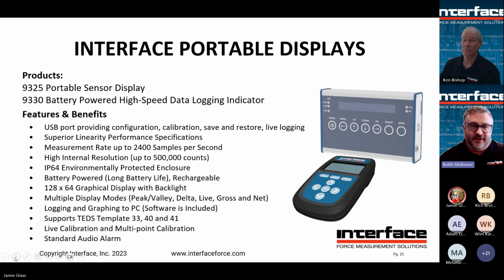It would be useful if you had, say, multiple load cells, but you only had one display and you wanted to walk around and plug your display into each load cell and take a reading. What TEDS does is it allows the instrument to self-scale the load cell via data that's stored on the chip that's part of the load cell. And so the instrument can be turned on and take a reading, then you could disconnect it, walk over to the next device, plug it in, turn on, and take another reading.